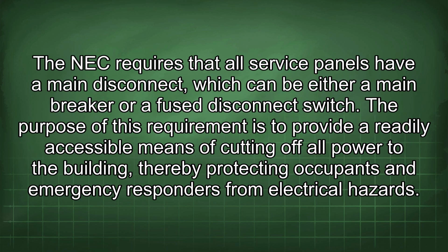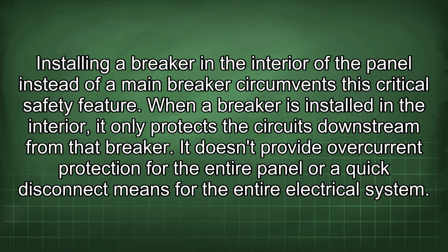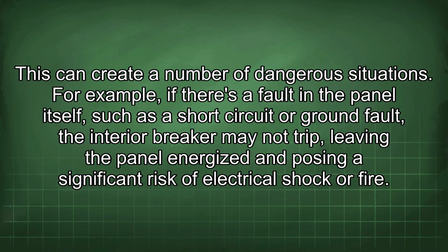The NEC requires that all service panels have a main disconnect, which can be either a main breaker or a fused disconnect switch. The purpose of this requirement is to provide a readily accessible means of cutting off all power to the building, thereby protecting occupants and emergency responders from electrical hazards. Installing a breaker in the interior of the panel instead of a main breaker circumvents this critical safety feature. When a breaker is installed in the interior, it only protects the circuits downstream from that breaker. It doesn't provide overcurrent protection for the entire panel or a quick disconnect means for the entire electrical system. This can create a number of dangerous situations.